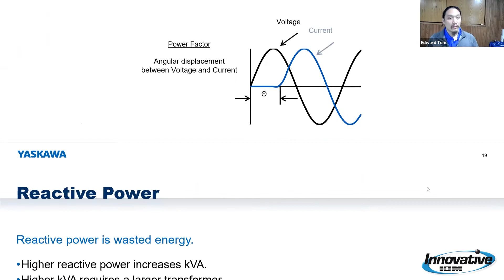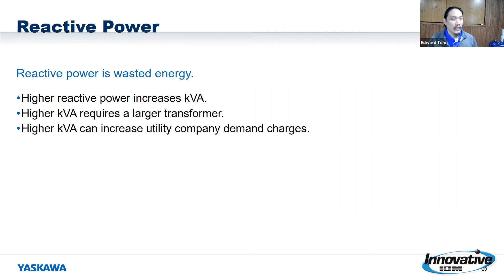So what does that mean? It means we're taking the reactive power - the energy just circulating inside - and trying to reduce it with the drive. Why is this reactive power a problem? Well, reactive power makes up the kVA, and that's what power companies charge you for - how much you're sending out at that moment. The more kVA it needs to supply, the more you're charged, and it also means a larger transformer is needed to supply you, along with higher demand.